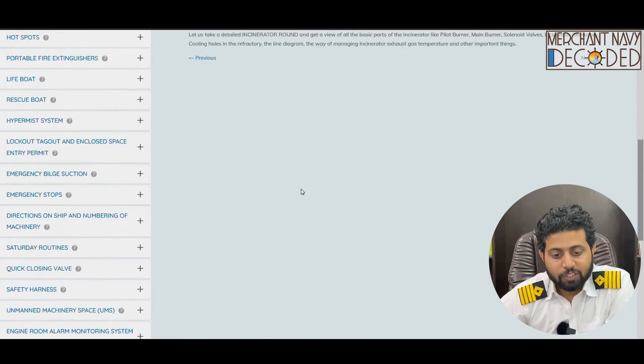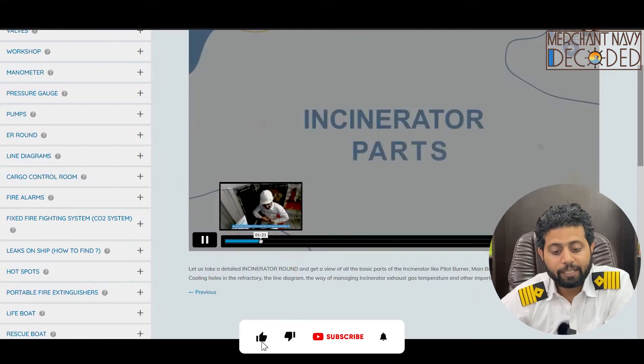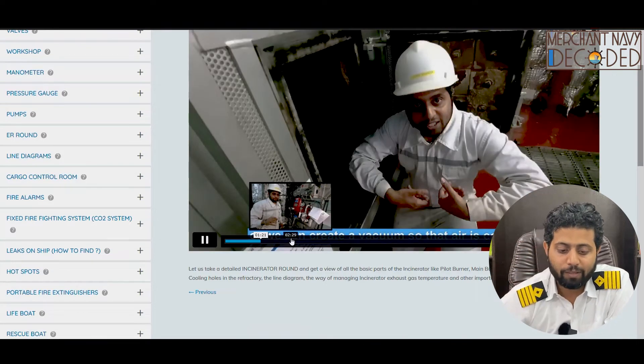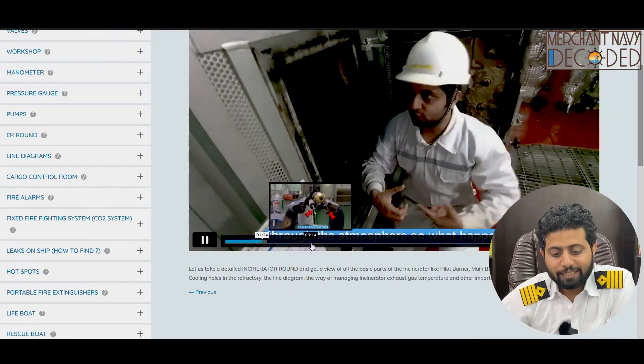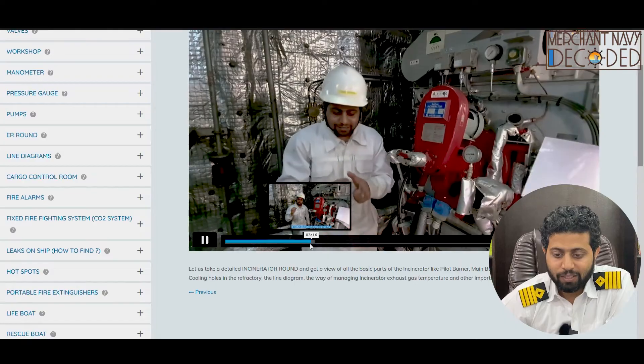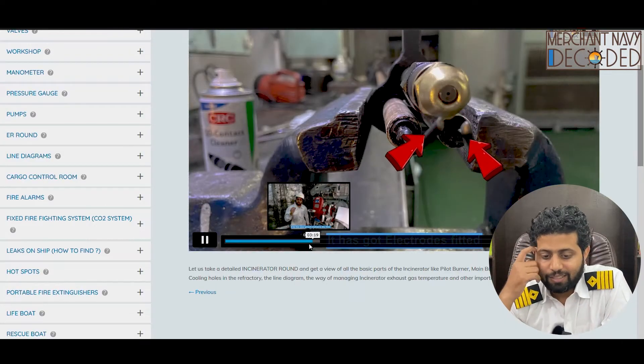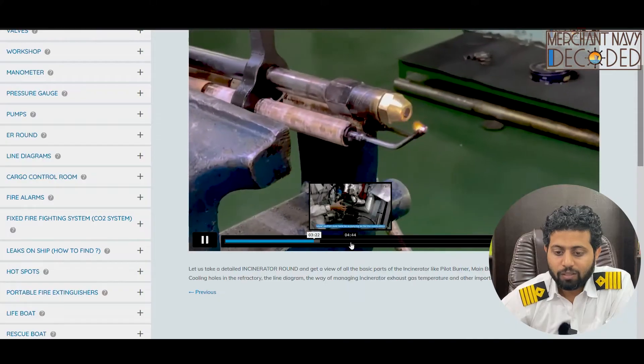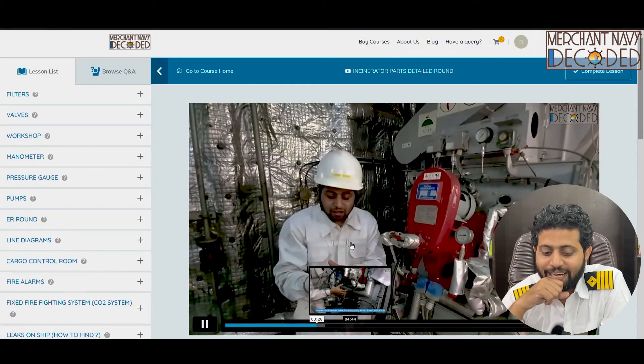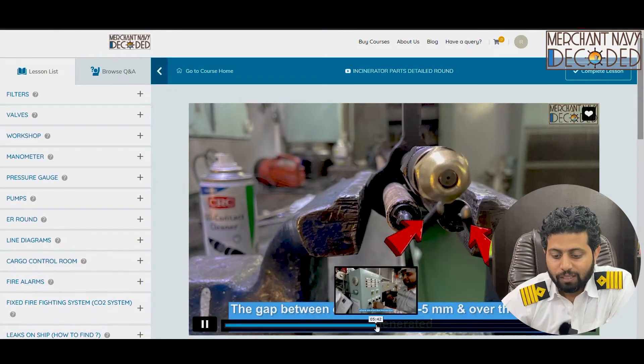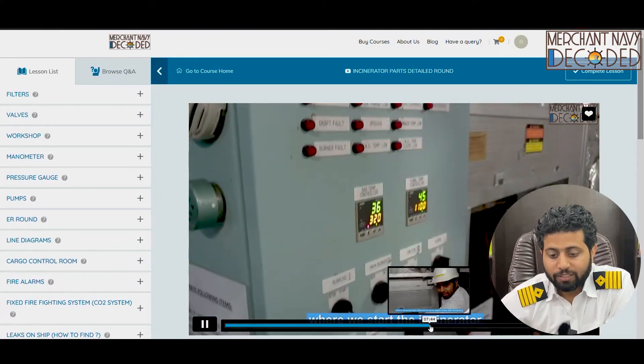The second incinerator video discusses each and every part in detail: the refractory, the main burner, the pilot burner. How does a pilot burner work? How does a main burner work? This is an automation part — a spark is generated by 10,000 volts between two electrodes. The incinerator main control panel is also shown, covering what alarms are there, how an incinerator starts, and how an incinerator fires.